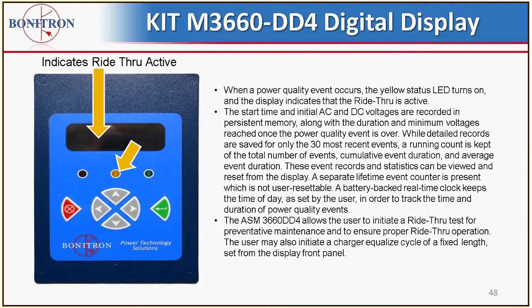It also allows the user to initiate a ride-through test for preventive maintenance and to ensure proper ride-through operation is the case. So in other words, during test, it's doing a brief boost function, and the amber light will light, indicating that it's actually boosting properly during ride-through test. The ride-through test is a preventative maintenance function, and it ensures the proper ride-through operation. The user can also initiate a charger equalize cycle of a fixed length set from the display front panel too.